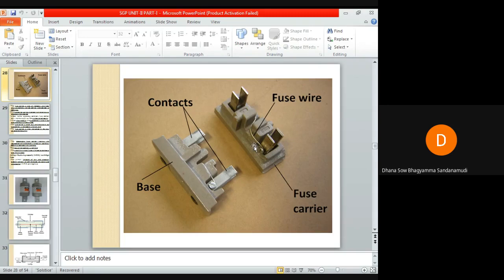What is tinned copper wire? We have already discussed in the earlier classes. In between these two terminals, a tinned copper wire is fixed, which is the fusing element. And this fuse carrier, after placing this tinned copper wire in between these two terminals, is inserted into the base. So under normal operating condition, where current is flowing through this fusing element, that is tinned copper wire, the tinned copper wire will not get overheated. Of course, the temperature of the copper wire may increase, but it will not reach its melting point.